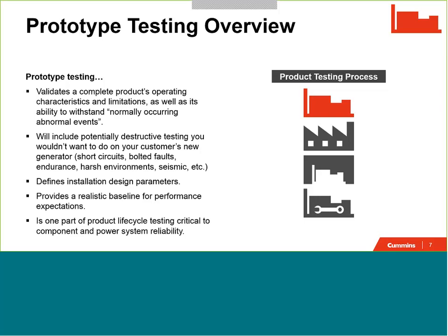Prototype testing will often include potentially destructive testing, and that's key to note because sometimes we do see testing requirements specified for a non-prototype, for the product that you or your client is purchasing. And when that testing is potentially destructive, we often recommend leaving that to the prototype product and not conducting that potentially destructive testing on your actual product. I'll talk more about potentially destructive testing here in just a short bit.